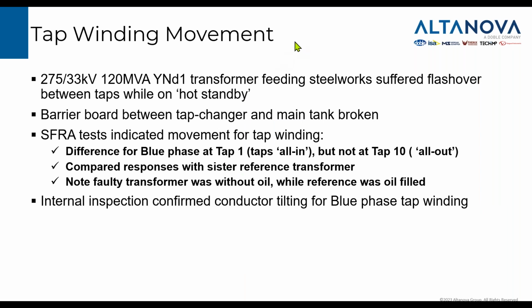And here, last example. In this case, we identified tap winding movements. So this was a 275 down to 33 kV, 120 MVA transformer feeding steelworks, and it suffered flashover between taps while being kept on hot standby. It was opened, and the barrier board between the tap changer and main tank was found broken. SFRA tests indicated movement of the tap winding.